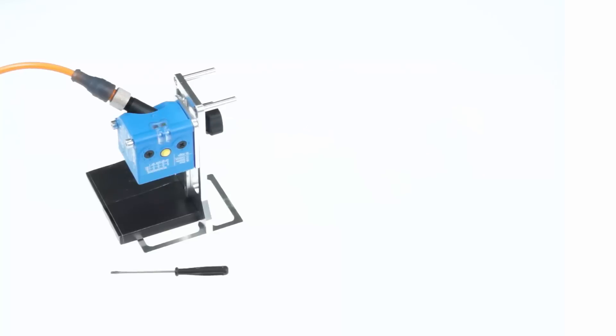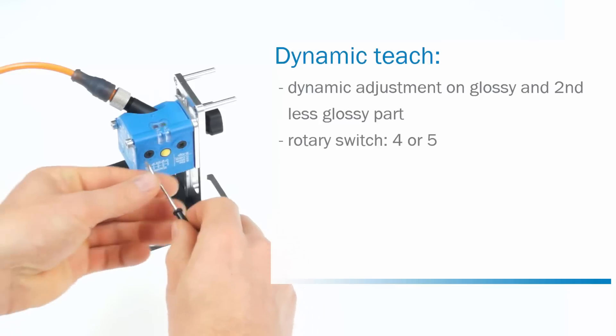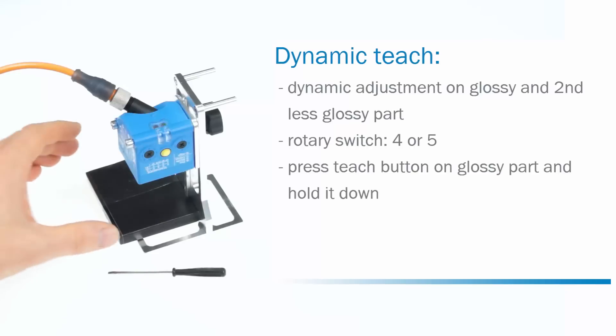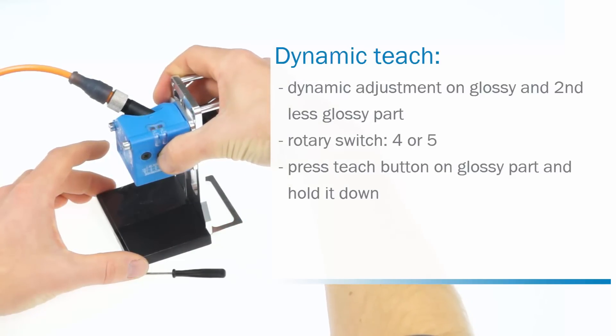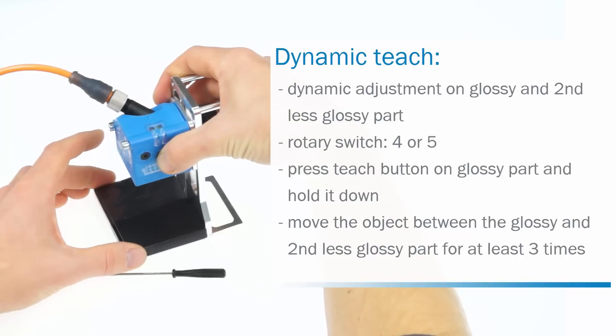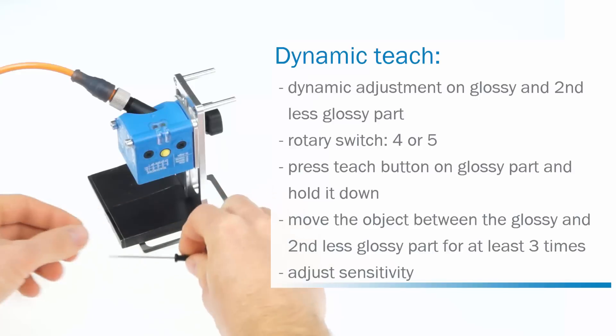The fourth method is the dynamic teach. This method requires dynamic adjustment on the glossy part that shall be detected as well as on the second less glossy part of the object. It is used for applications where a teach-in is only possible during a running process. Set the rotary switch to four, or respectively five for the inverted Q output. Move the glossy part of the object under the light spot, press the teach button, and hold it down during the whole teach-in process. The yellow LED starts flashing. While holding the button down and the LED flashes, move the object between the glossy and the second less glossy part. After at least three moves, release the button. The setting is finished. The sensitivity can be adjusted by setting the other rotary switch to A, B, or C.